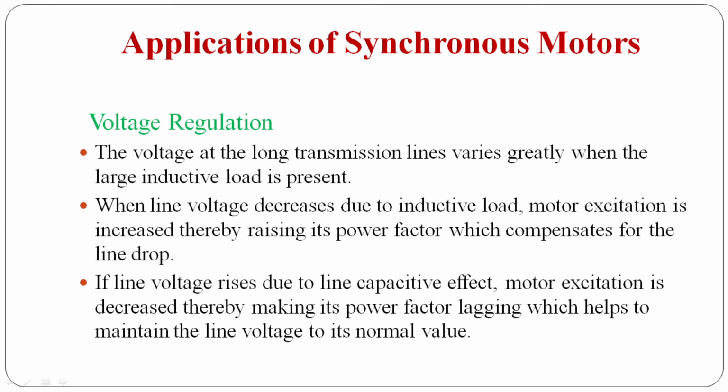So next is voltage regulation. The next application of synchronous motors is voltage regulation. The voltage on long transmission lines varies greatly when a large inductive load is present. When line voltage decreases due to inductive load, motor excitation is increased, thereby raising its power factor, which compensates for the line drop. If line voltage rises due to line capacitive effect, motor excitation is decreased, thereby making its power factor lagging, which helps to maintain the line voltage at its normal value.